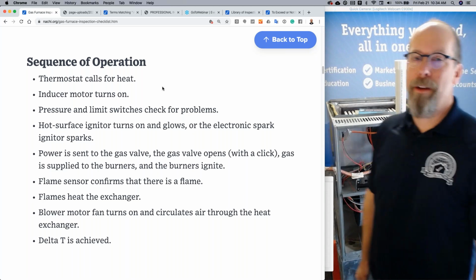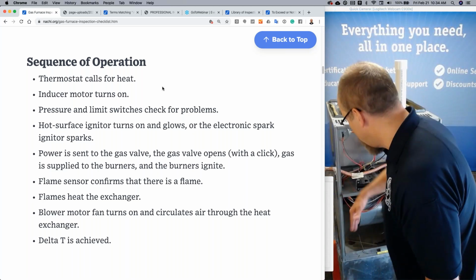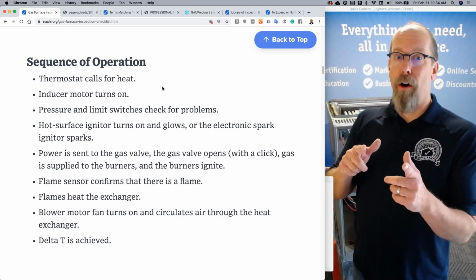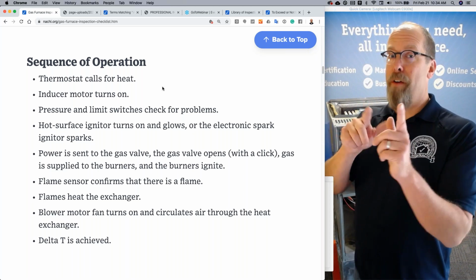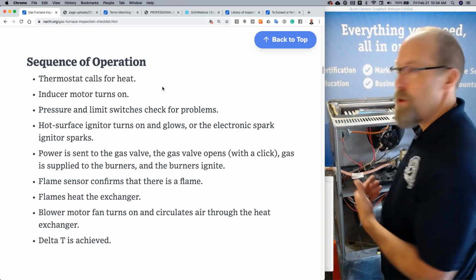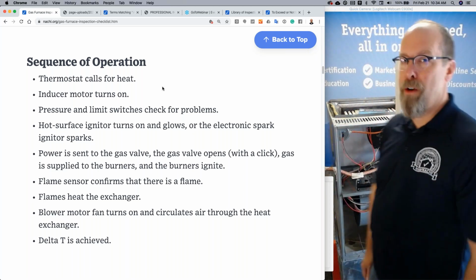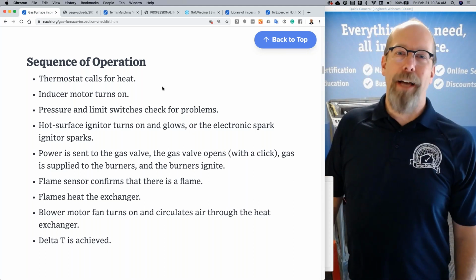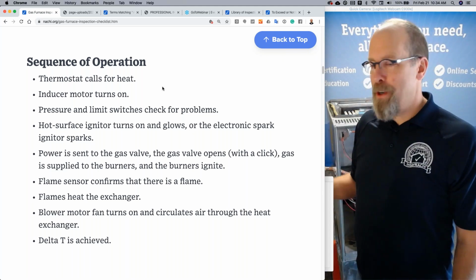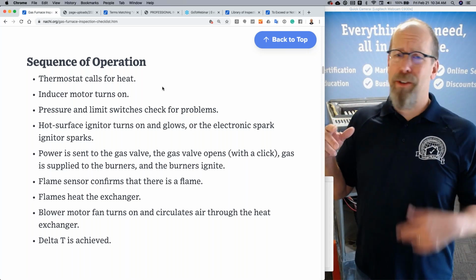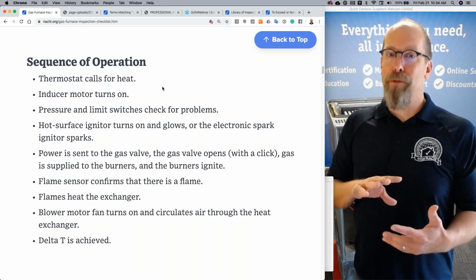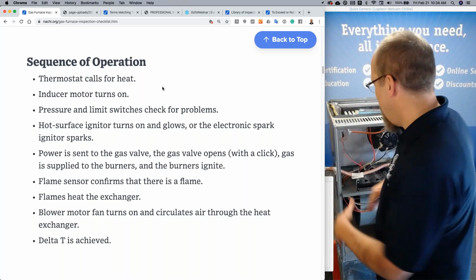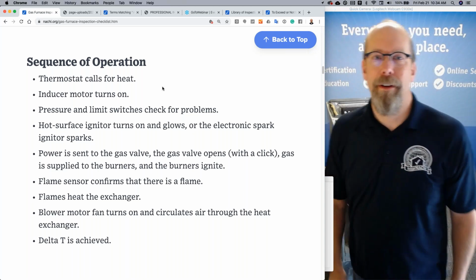And that's how I do it. So I turn the system off, call for heat at the thermostat, come back, turn the unit on, and watch the sequence go through. And I don't heat up the entire house. If it's wintertime, it's already warm. If it's summertime, I'll turn it on momentarily, and I'll put that restriction in my inspection report, and then I'll turn it off. So it's safe.